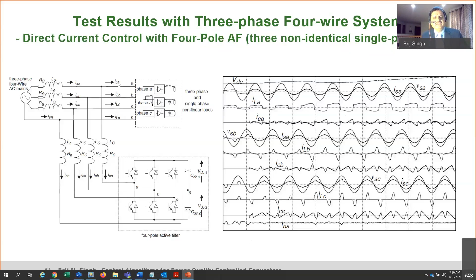So neutral is closed. Here we have three different loads, right? First phase is RL, second is RC and linear, and third is plain RC. So with three different single-phase loads, different types, the converter will still be able to compensate. Phase A will provide current like this, phase B like this, phase C like this. Since it's in current control mode, the power lines will force themselves to behave like a source like this, and the neutral current will look like this. So if you put this into current control mode, it will provide what you need.